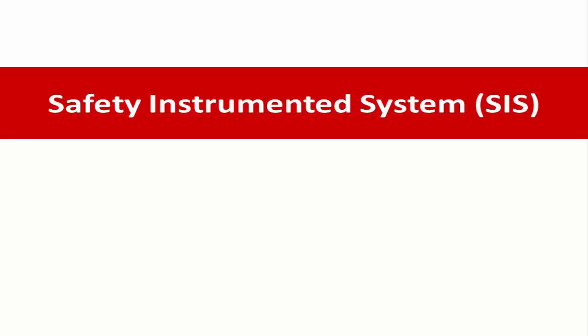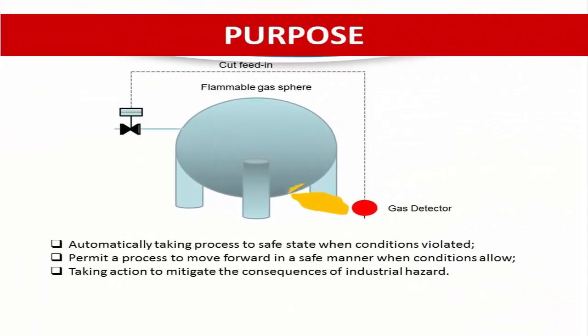Safety Instrumented System, or SIS. The definition of the Safety Instrumented System as defined in ANSI/ISA 84.00.01 or IEC 61511 is an instrument system used to implement one or more Safety Instrumented Functions, or SIFs. A SIS is composed of any combination of a sensor, logic solver, and final element.